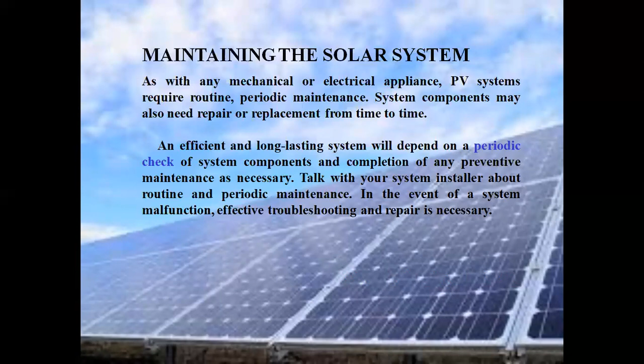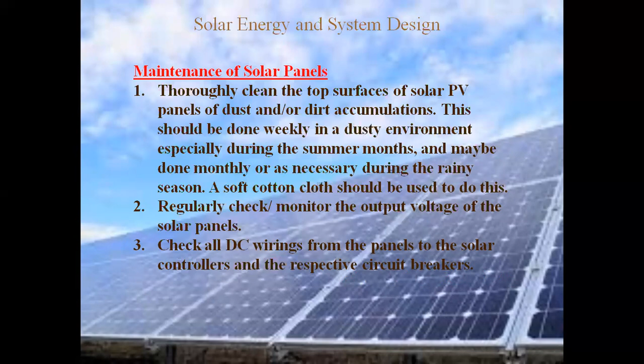So these are the items on the maintenance list for solar panels. Number 1, thoroughly clean the top surfaces of the solar PV to remove accumulated dust and dirt. Number 2, regularly check and monitor the output voltage of the panels and inverters. Check the wiring connections - if they're loose, you need to retighten them, because if you don't, it can cause arc flash and short circuit.